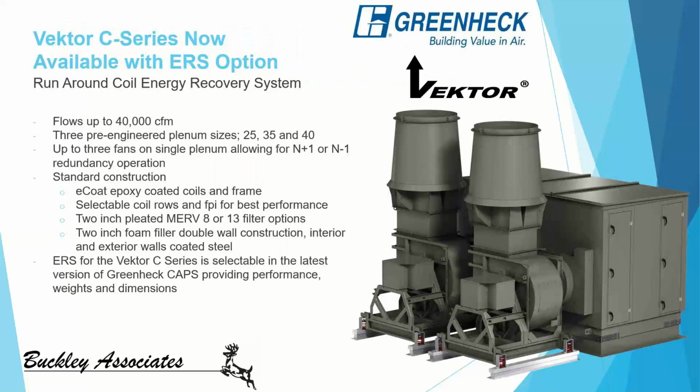So the first of those new energy recovery options is we're now able to provide the Vektor C-Series fans with a factory-built ERS option. Basically, this is a runaround energy coil. And this gives us flows up to 40,000 CFM in three pre-engineered plenum sizes. We can do up to three fans on that single plenum, allowing for N+1 or N-1 redundancy. All the standard construction still applies as it did on the Vektor ERS systems. We can do MERV 8 or MERV 13 filters, and this is actually now selectable in caps.